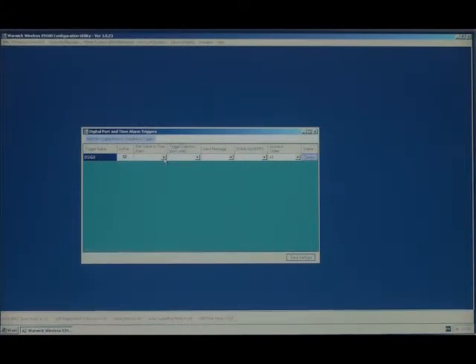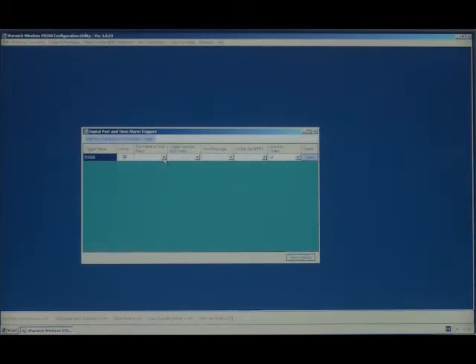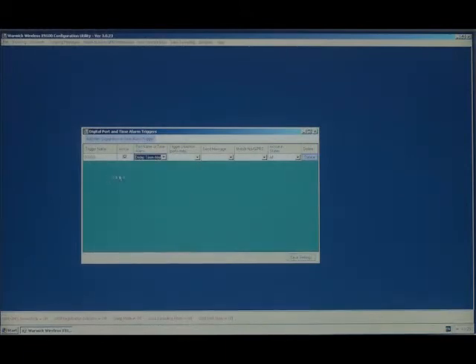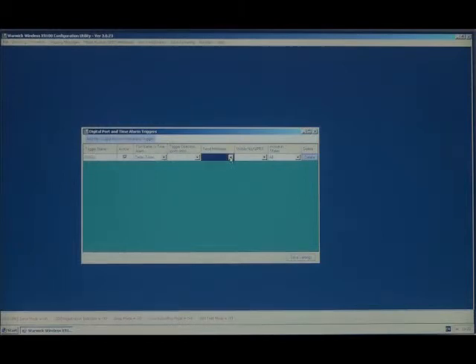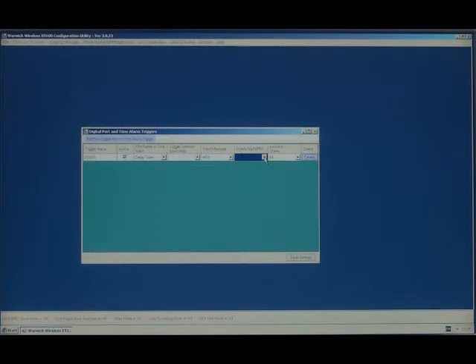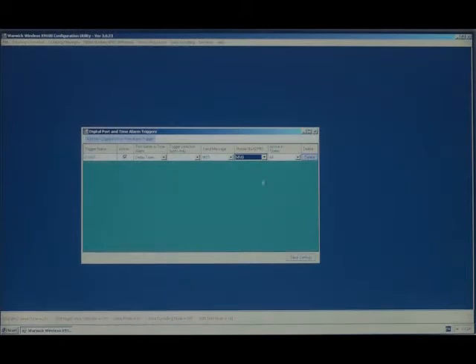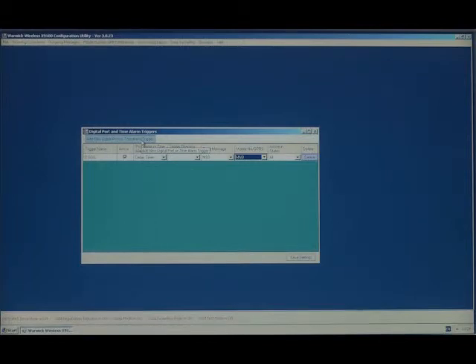We click on Outgoing Messages, Digital Port and Time Alarm. On the port name or time alarm, we select Delay Time Alarm. The trigger direction is left blank. And we're going to send the message MS0 to Mobile Phone GPRS Address MN0. That will send the message every time the delay timer is triggered to the mobile phone.